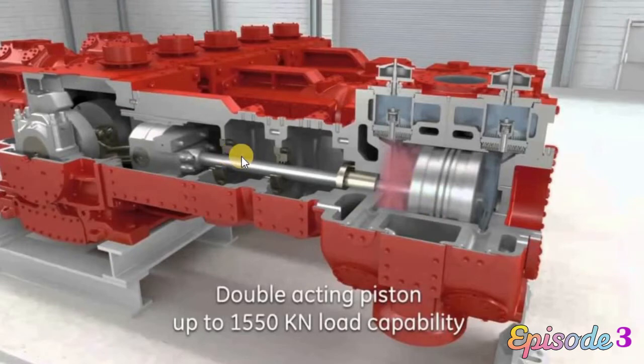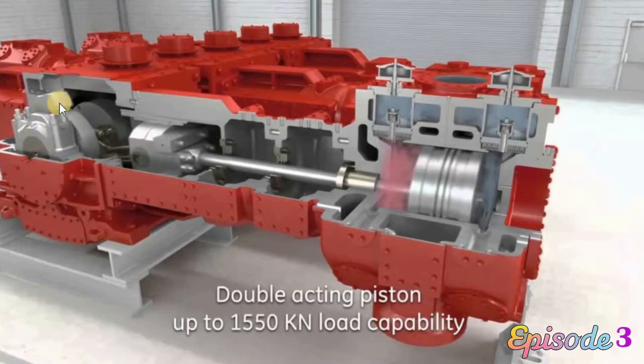This is a reciprocating compressor. You may say this is a piston, this is the piston rod, this is the crankcase, and this is the crankshaft, inside the crankcase. So this is very important. We use the reciprocating compressor where we have to increase the pressure but the flow is very low. In the centrifugal compressor, the flow is high but the pressure is lower than the reciprocating compressor.